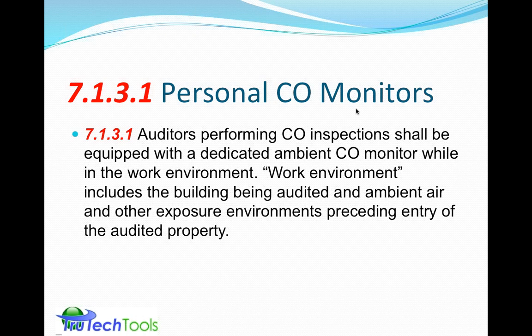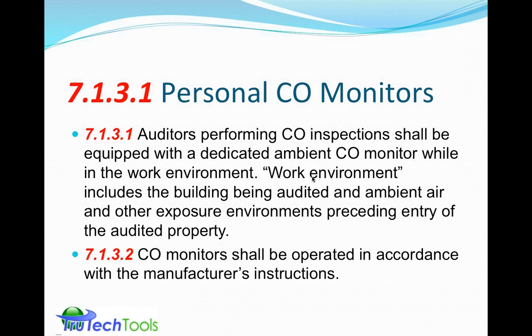We also see the description in the standard, 7.1.3.1, where it discusses personal monitors, where the auditors performing CO inspections shall have a dedicated ambient CO monitor while working in the work environment. And then it describes the work environment, preceding entry into the audit, looking for exposure in the environment preceding entry, as well as inside the building being audited and the ambient air. So it's important to be sure you have a dedicated personal CO monitor.